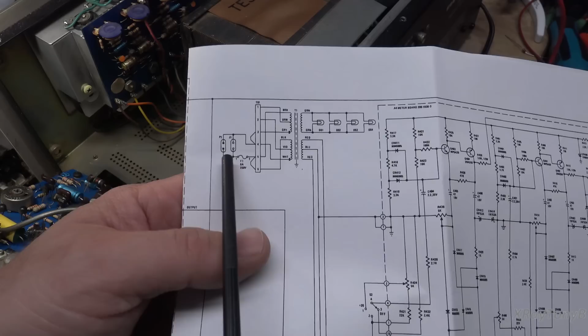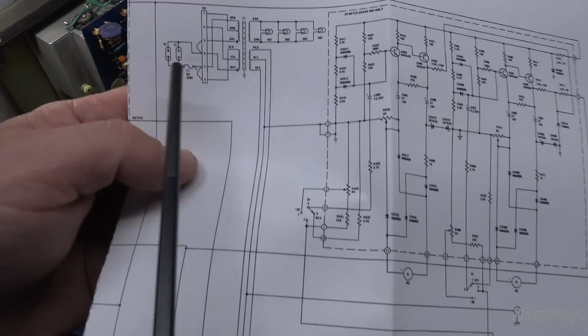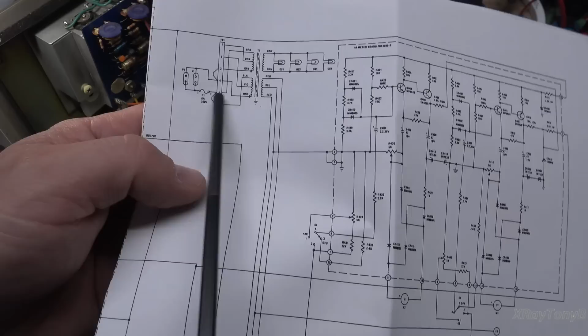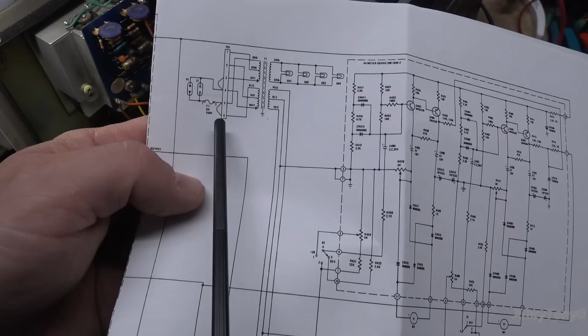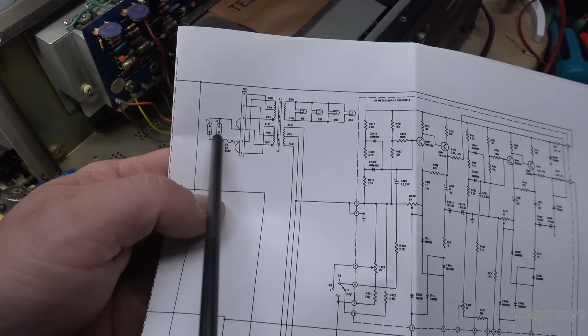And then we want another thing to control that, because once these caps have started to charge and that inrush current has started to drop, we want to take that resistor out of the circuit to allow full power to the amplifier, so you're not drawing current through that resistor all the time and heating it up. To do that, we're going to use a relay that's going to short out that resistor and just make it look like a straight wire again.